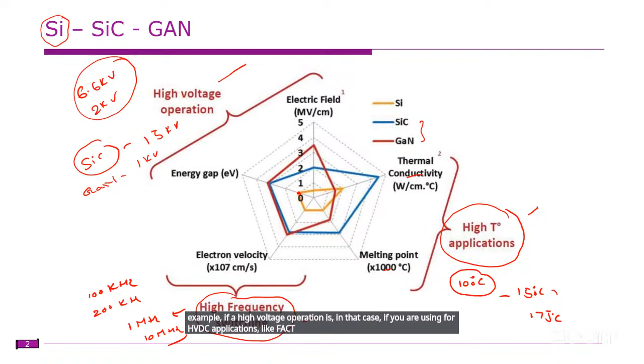For example, for high voltage operation in HVDC applications like FACTS or other applications, you need to connect several devices in series to cater to the required voltage. If devices are available with high voltage rating, the number of devices connected in series is much reduced. If the number of devices is reduced, the size reduces, power density increases, and reliability increases.